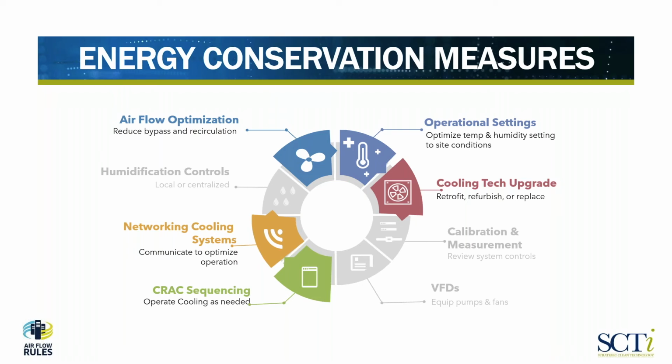Tied in with that, of course, depending upon the vintage of the CRAC units as well, we look at doing cooling tech upgrades. We've sent out, again, information on our website is available on that, which we refer to as a floating head retrofit. And that's taking a slightly older version crack unit and replacing some of the original components with new components, which are being used in the newest CRAC units on the market, and making that unit operate more efficiently.